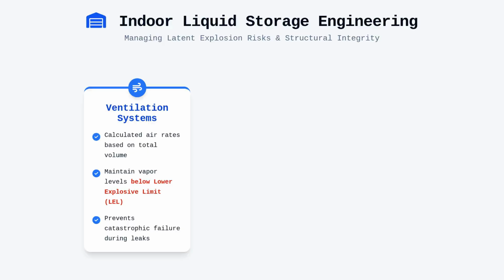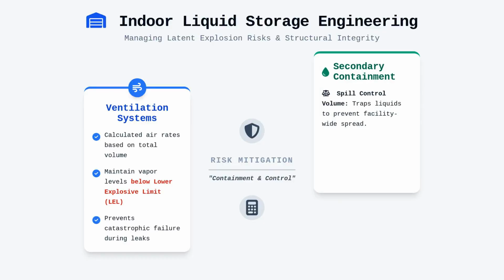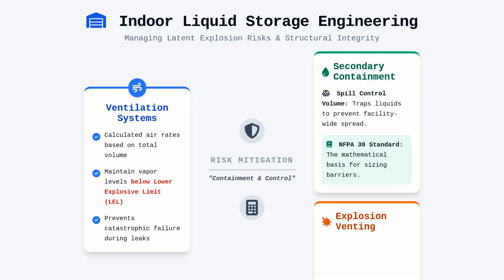Beyond ventilation, we must account for secondary containment, which involves calculating the spill control volume to ensure that, should a tank or barrel fail, the liquid is trapped within a controlled area rather than spreading throughout the facility. This is not just a suggestion, but a requirement for limiting the magnitude of a loss event, and the NFPA 30 standard provides the mathematical basis for sizing these containment barriers. We also emphasize explosion venting, which is designed to direct the overpressure from an internal flash fire safely away from structural members.